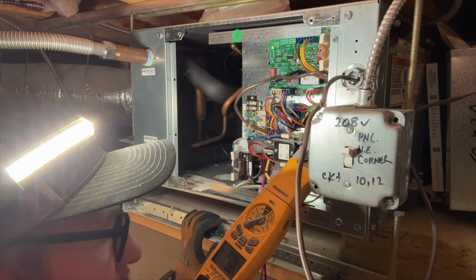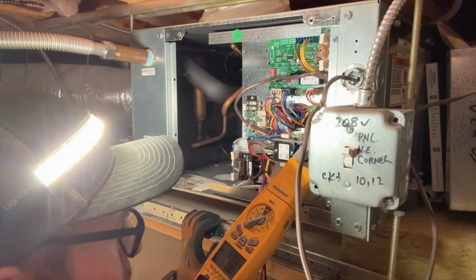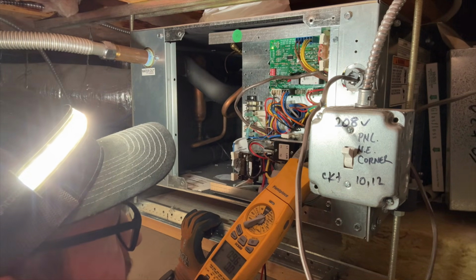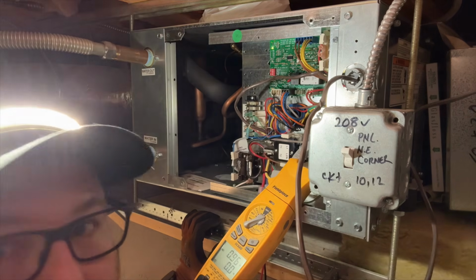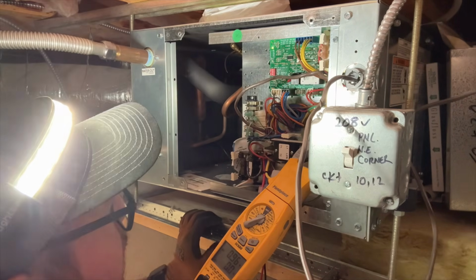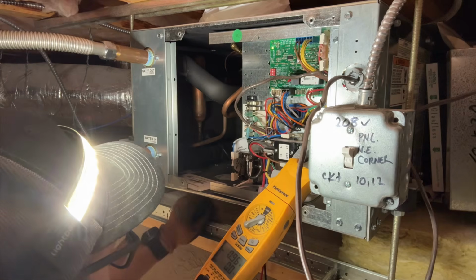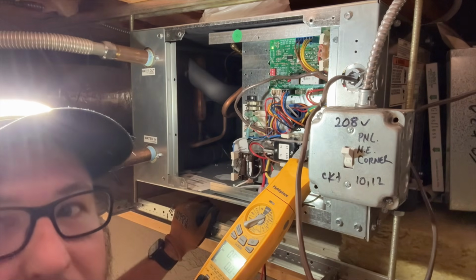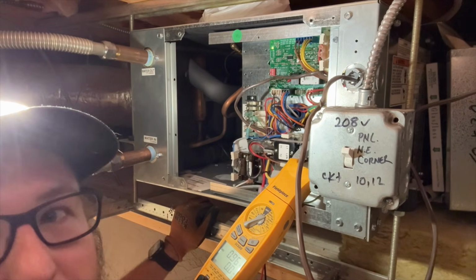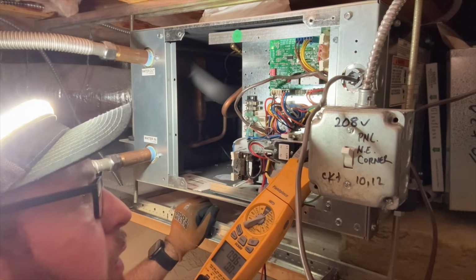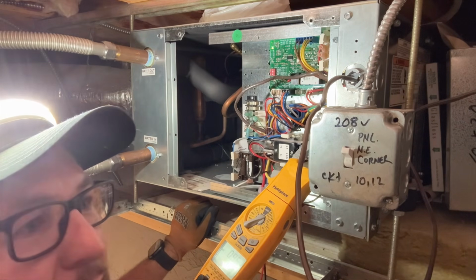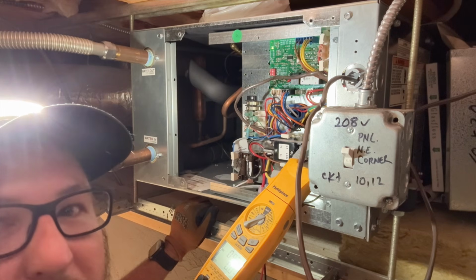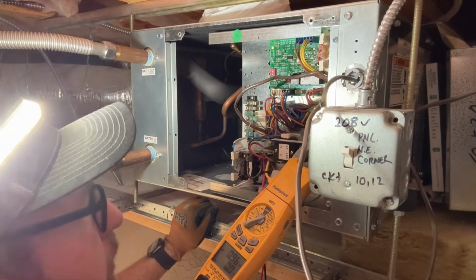So the current right now, just the fan is running, and the whole system is pulling about 0.96 amps, and that's just, you know, the transformer and the fan and everything. So everything's looking good so far. So after I've verified this, I'm going to start pulling and wiggling some wires. Maybe we have an intermittent short somewhere where it vibrates and shorts out to something.